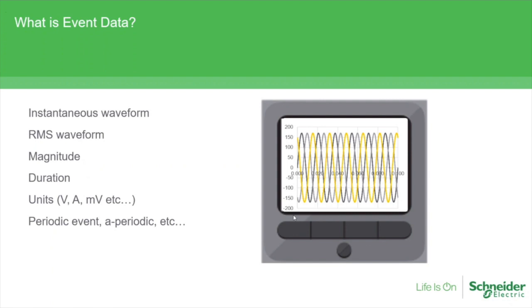So the 8650C meter, as an example, has a swell event log, but not necessarily the waveform capture. And the event log is going to have your more statistical information. It's going to tell you when the event happened. It's going to tell you how long the event lasted, usually in seconds, and then your min and max values for your voltage. And then just being aware of your units, whether it's volts, amps, power.